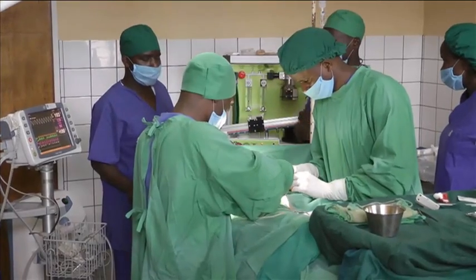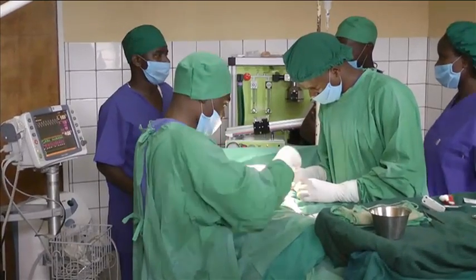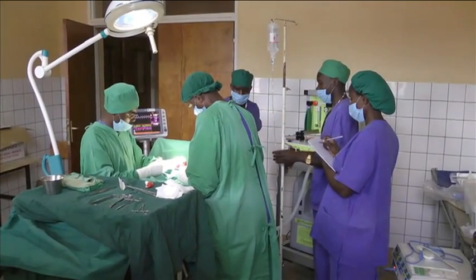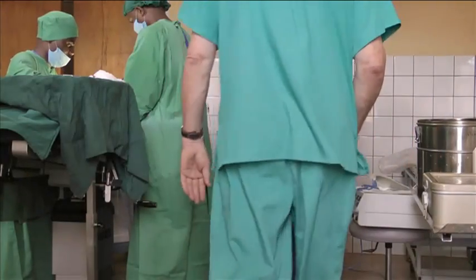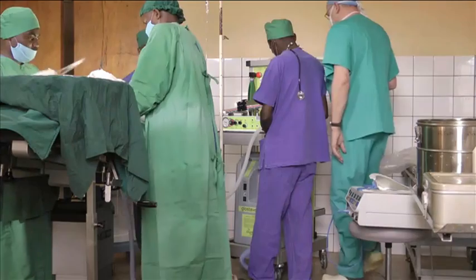The Glostavent machine being used in this operation in Rwanda requires minimal maintenance. It uses oxygen from the air rather than from a metal cylinder that may have had to be transported many miles to get here, making the Glostavent much safer and cheaper to run.